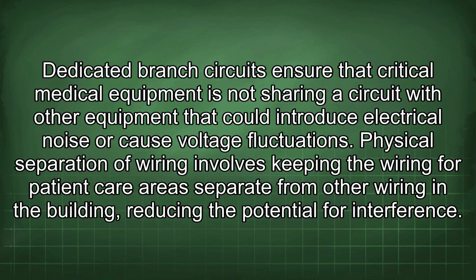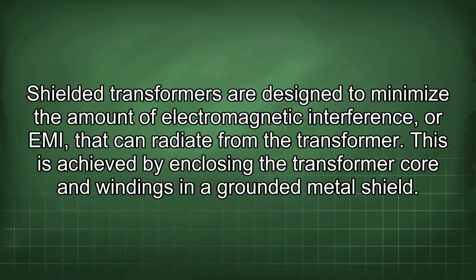Dedicated branch circuits ensure that critical medical equipment is not sharing a circuit with other equipment that could introduce electrical noise or cause voltage fluctuations. Physical separation of wiring involves keeping the wiring for patient care areas separate from other wiring in the building, reducing the potential for interference. Shielded transformers are designed to minimize the amount of electromagnetic interference, or EMI, that can radiate from the transformer. This is achieved by enclosing the transformer core and windings in a grounded metal shield.